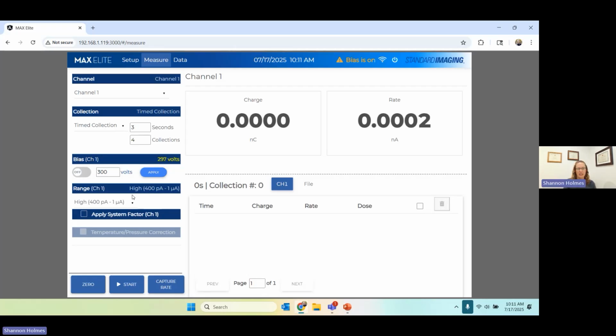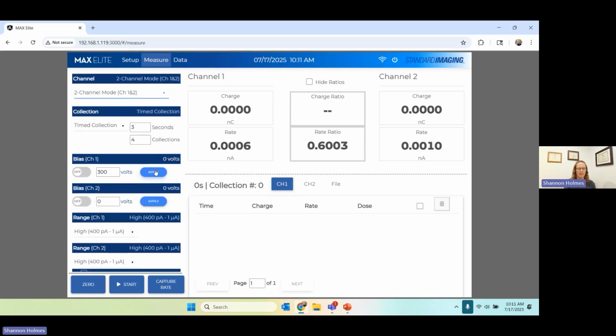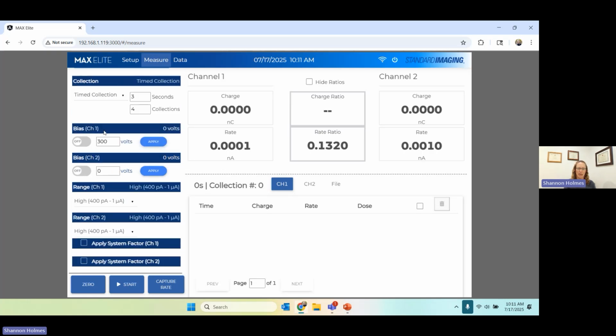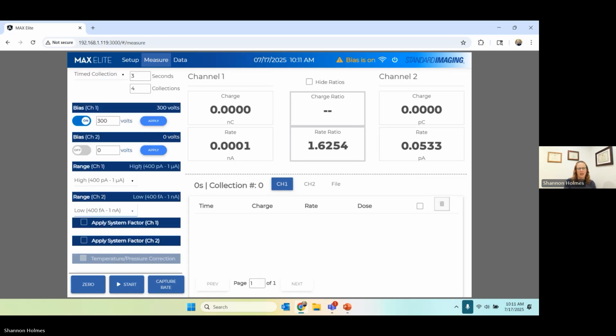You can select ranges, as I mentioned, independently for channels 1 and 2. Let me show you what that looks like here. If I have 2 channels, I have independent bias settings for those, so I could turn on bias on 1 channel and not the other if I'm using a diode or something like that. Choose my ranges appropriately for those 2 as well.